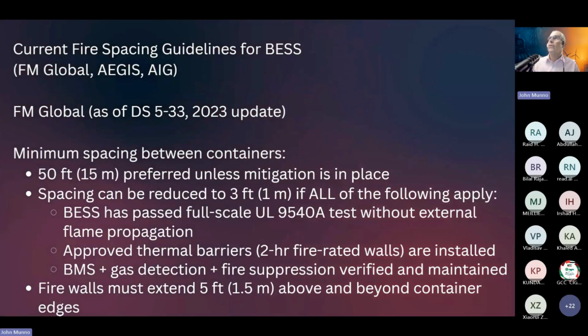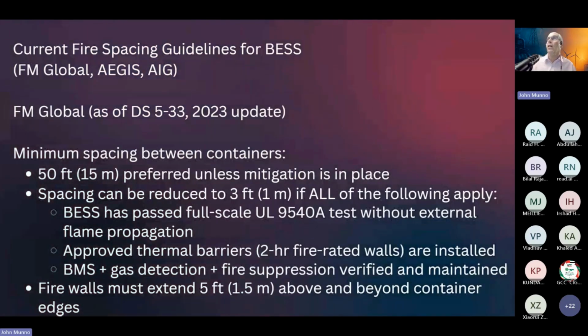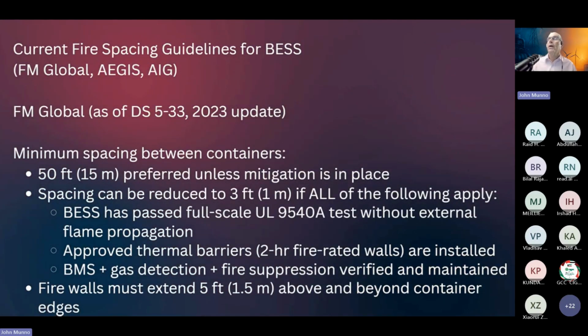All right, now let's talk about current fire spacing guidelines. I wrote a paper on this that got a lot of recognition on LinkedIn. So FM Global is one of the companies that looks at batteries. AEGIS, that's the Associated Electric Gas Insurance Services, and AIG. They all are large global insurance companies, and they have different guidelines. And it's interesting that they're going to have different guidelines. But FM Global prefers 50 feet unless you've got some kind of mitigation, such as having passed a full-scale 9540A test without external flame propagation, if you have approved thermal barriers, and if you have gas detection, BMS, and fire suppression.